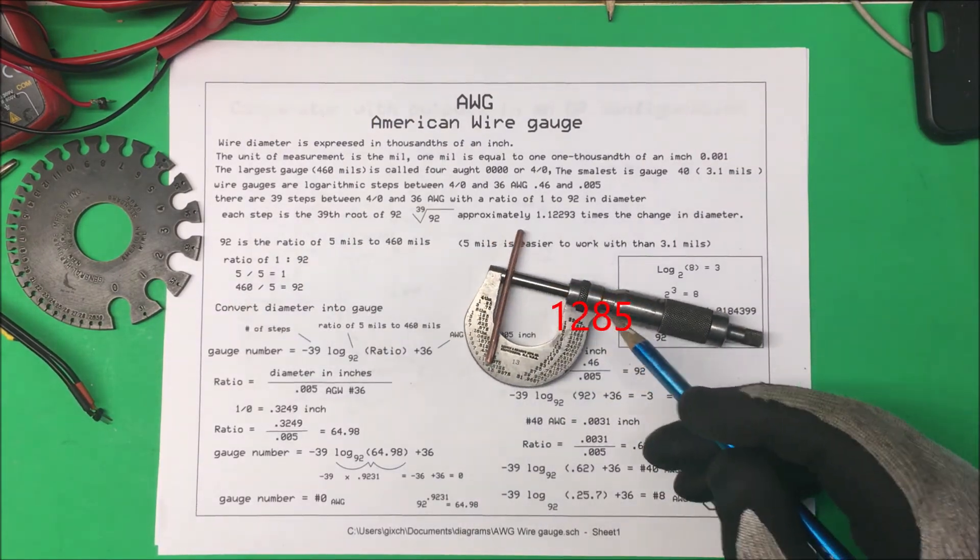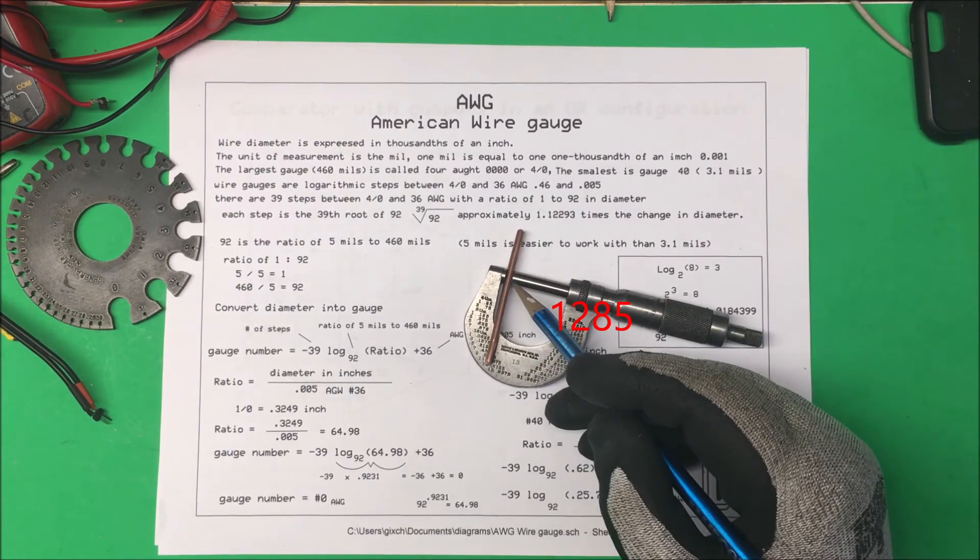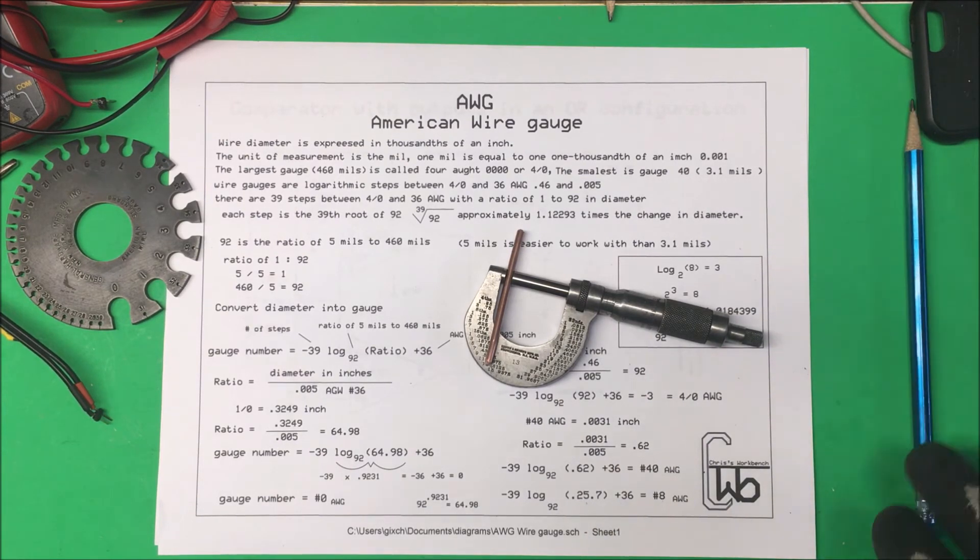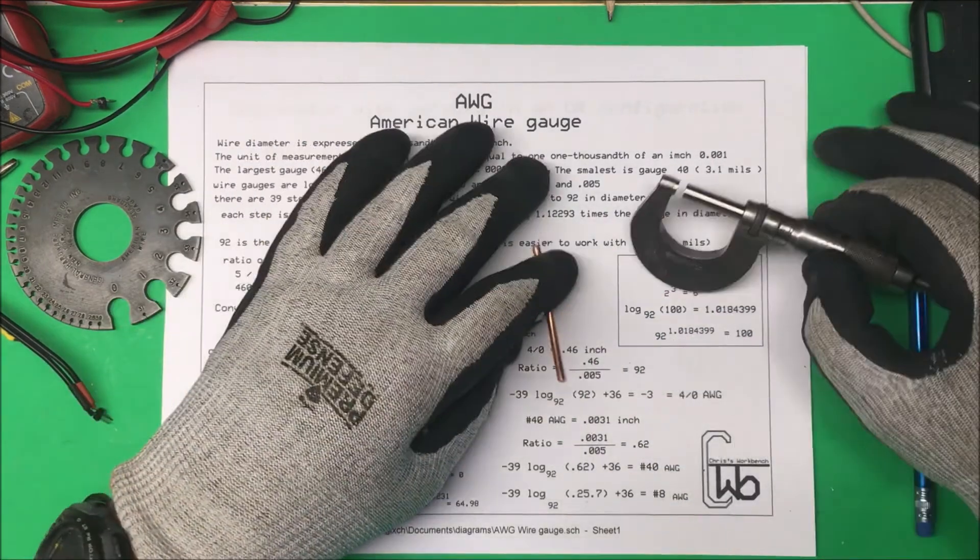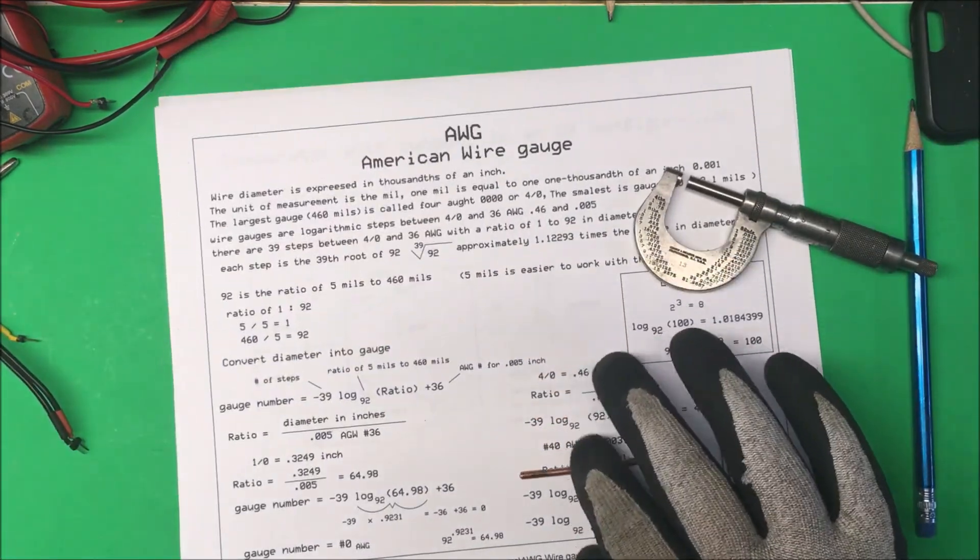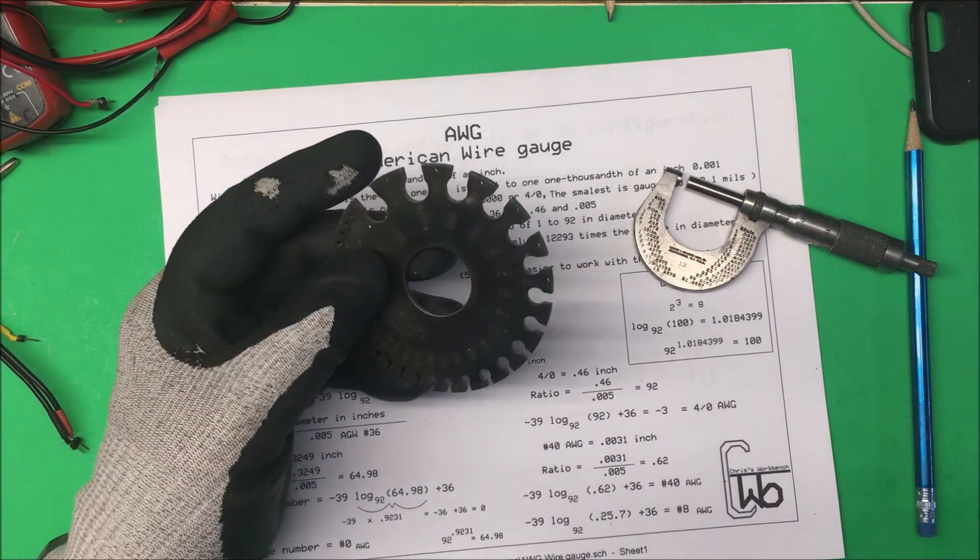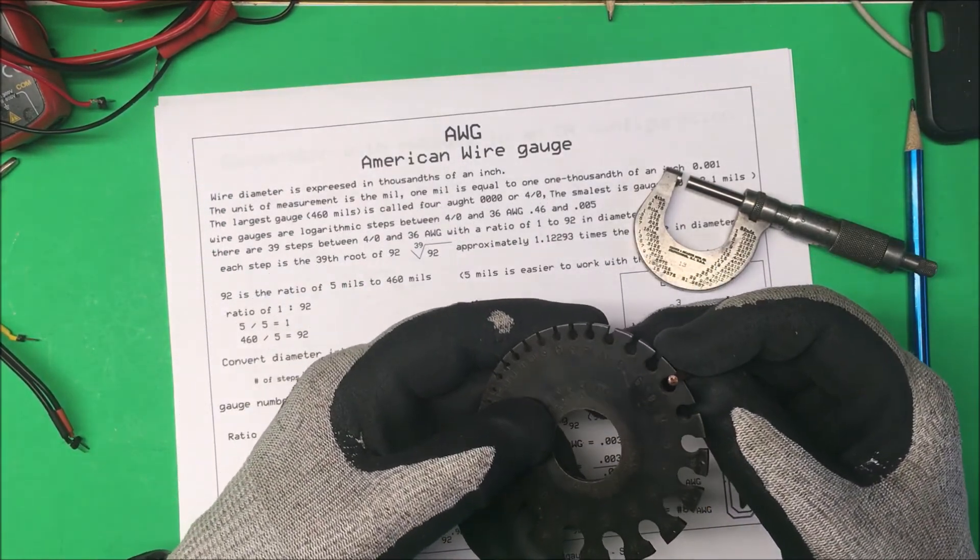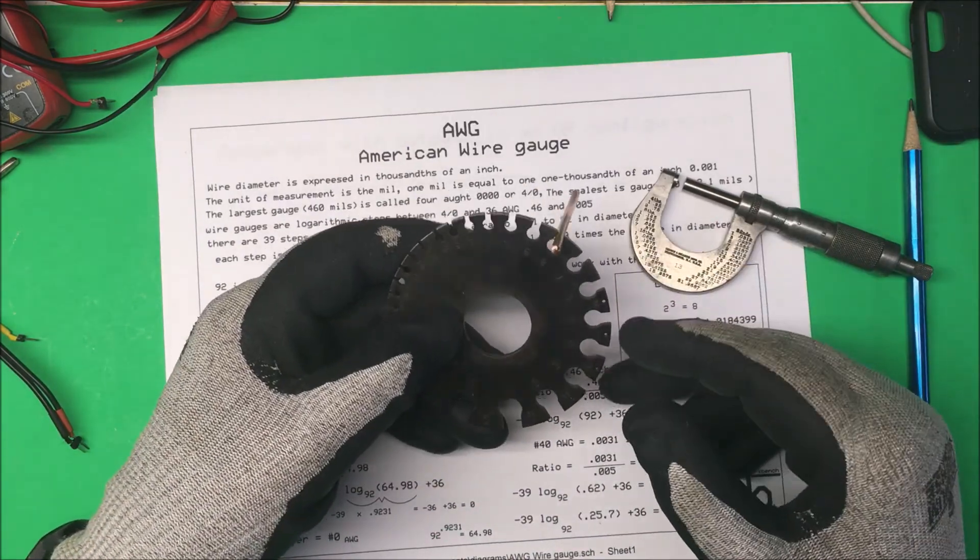If we take that diameter and divide it all out and put it into the formula it comes out to eight AWG so this is number eight wire. Of course we can test it on this unit here a lot easier, it just gives it right to you and eight should be there, yep that's eight right there.